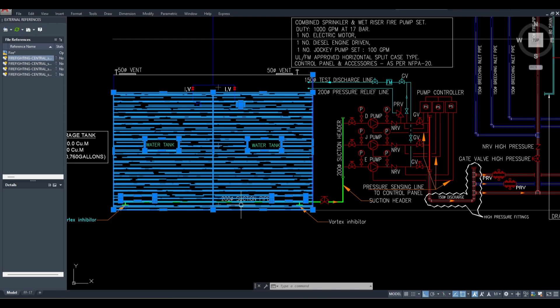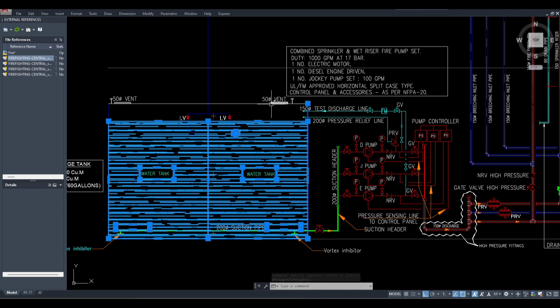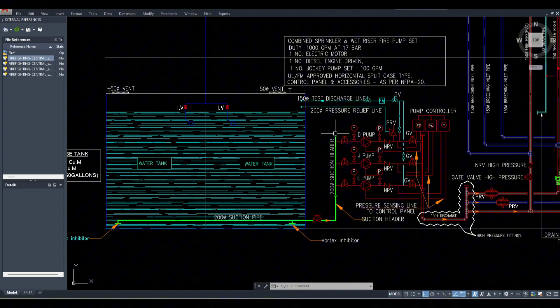There is a rule for this: 10% below the volume you leave at the bottom as extra water that you consider unusable, and 10% above you keep as freeboard area since you don't want to fill the water to the very top of the tank. So 10% extra below and 10% extra space above, keep these two in mind. Whatever volume is coming after that is the actual water volume. So suppose they have given 75,000 liters, then 75,000 plus 20% should be the volume of your water tank. So that's one thing you learned.